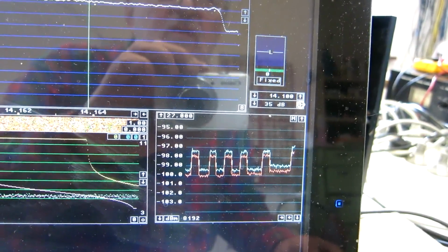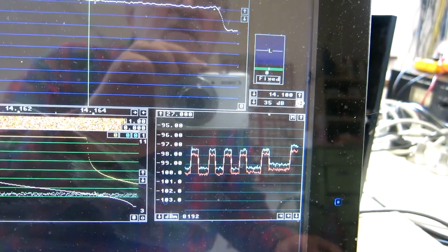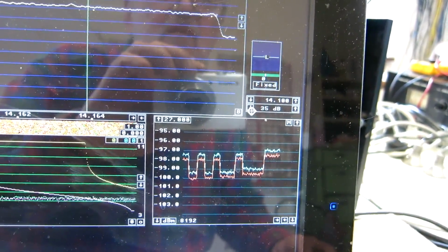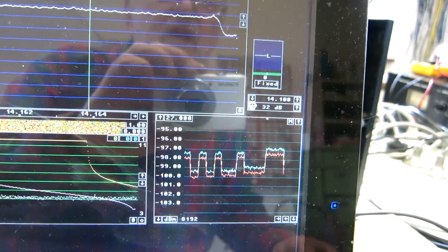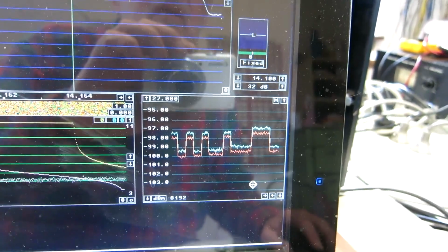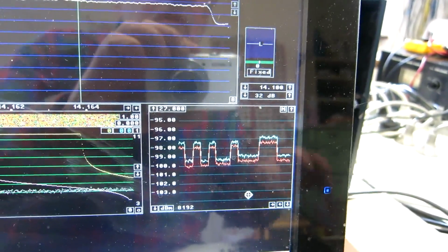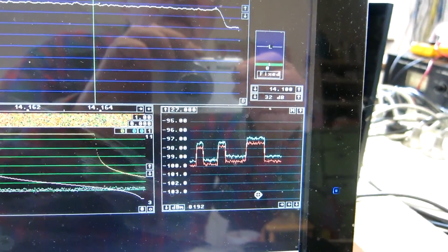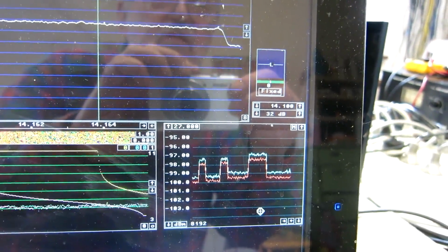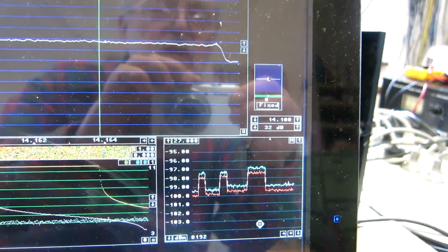So I increase again. And that's the highest gain. So the second highest gain is the most favorable gain setting for sensitivity. And it also gives very close to the full dynamic range, to within 0.3 dB or so.